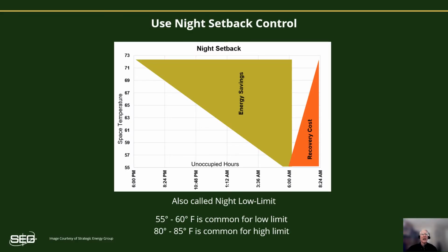We are occasionally asked, isn't it less expensive to run the building all night rather than to have to use a lot of energy heating it up every morning? And generally speaking, the answer is no, it isn't. Utilizing night setback control, or also called night low limit, offers a good trade-off as it maximizes your off time while not letting the building's mass get too cold during the night, which could otherwise require extended warm-up periods. And by keeping things off as much as possible, it allows savings to accrue all night long.